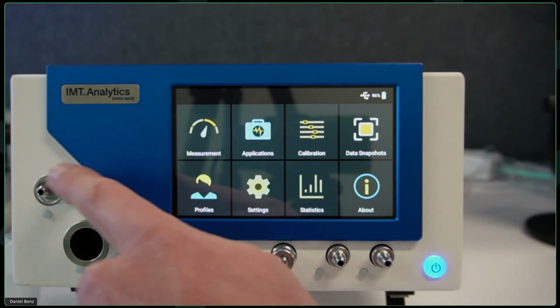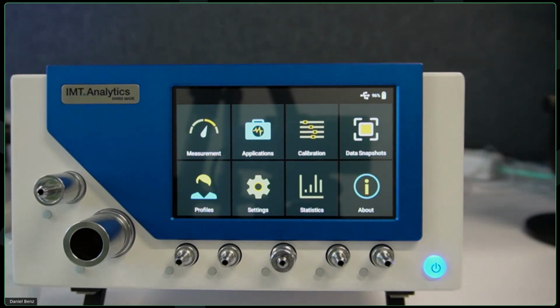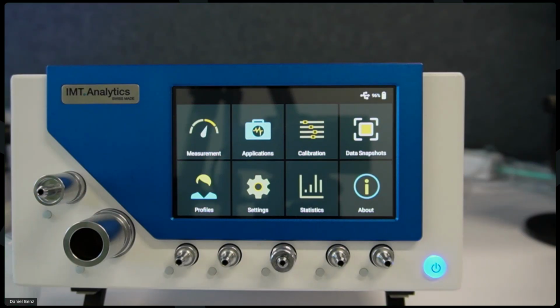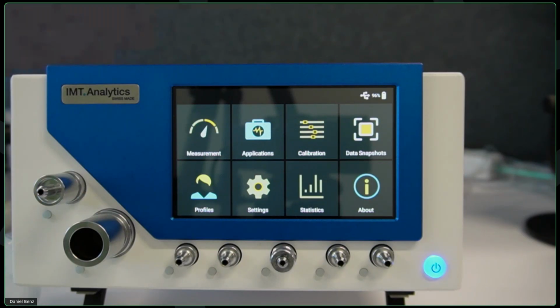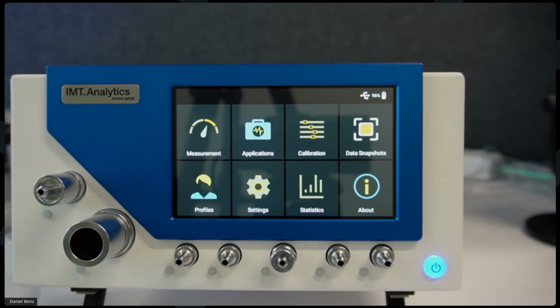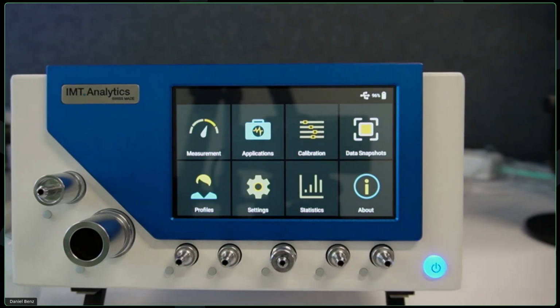Right next to this main flow channel port, we have another flow channel, and this is called the ultra-low flow channel. This is mainly used for anesthesia machine applications where it comes to measuring tiny flow rates, typically in the range of a couple of dozen milliliters per minute. The range of this port is plus minus 1 liter per minute with an accuracy of 1.65% or down to 10 milliliters per minute. Over here, we have our pressure ports.